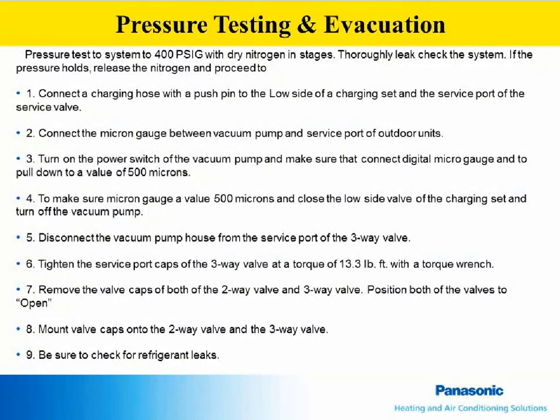Once your piping is completed, the system can be evacuated and leak checked. Pressurize the line set and the indoor unit to 400 psi with dry nitrogen and check the flare connections for bubbles by applying a soapy or leak detection solution. Ideally, we would like to have the system hold this pressure for 24 hours, but this is not usually practical. 30 minutes to an hour should be minimum before vacuuming.